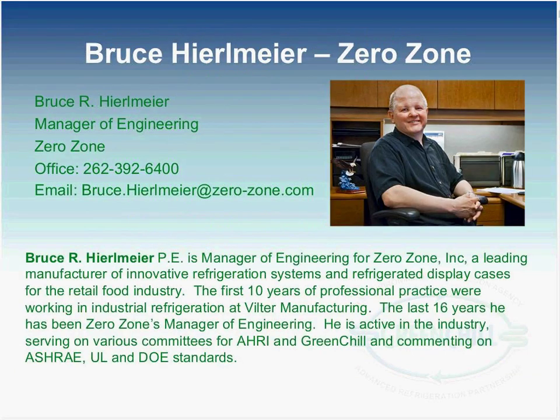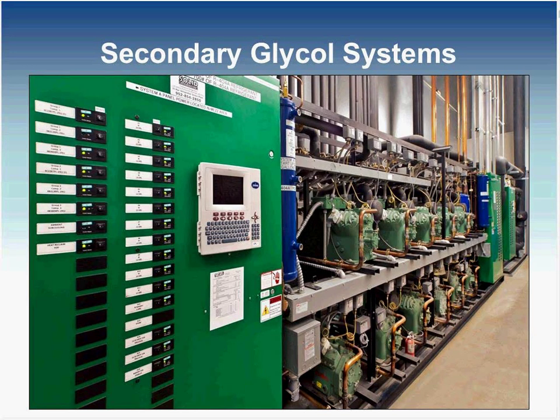Thanks, Keely, and that brings us right up to the slide here that we're going to talk about, secondary glycol systems. A lot of times they might be called simply a secondary system, since some of the first secondary systems were glycol. It's somewhat of a generic term, but usually it means a secondary loop system that's going to be for the medium temp. So it's going to be cooling your meats and your cheeses and that type of thing, things that need to be cold but don't want to be frozen. These systems, in the most generic sense, are typically going to be a central compressor system, much like we saw with the first DX system. And a rack will be designed to use an HFC gas, used as what we'd call the primary refrigerant.